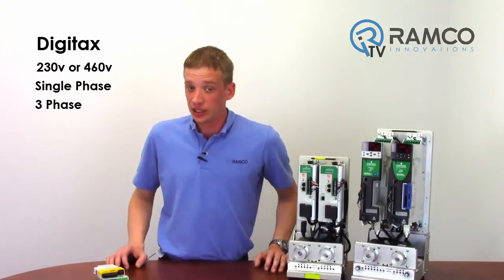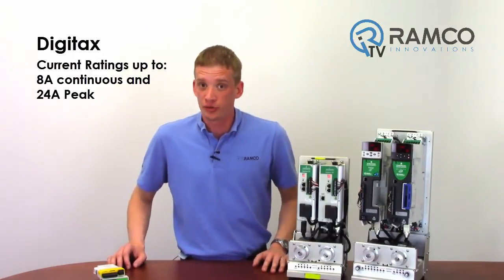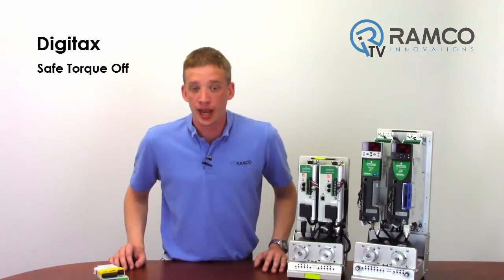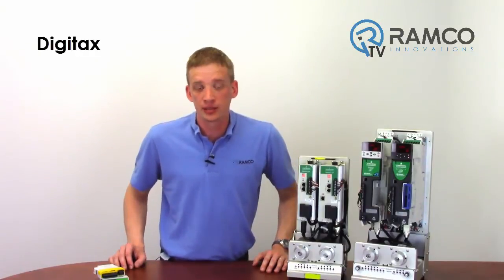The Digitax drives are 230V or 460V, offered in single phase or three phase. They can be ordered in current ratings up to 8A continuous and 24A peak. There are three user selectable inputs and three inputs that can be configured as status outputs. Analog inputs and outputs are available as well. This drive offers safe torque off for a safe internal disconnection of three phase power to the drive. There are also two additional solution module slots which can be configured to expand I/O, provide universal encoder feedback, add an Ethernet port for Ethernet IP interface, and more.